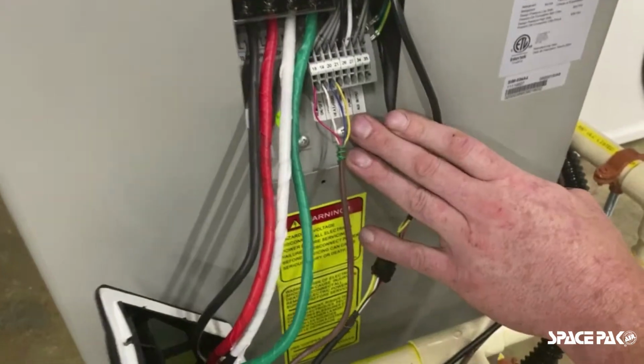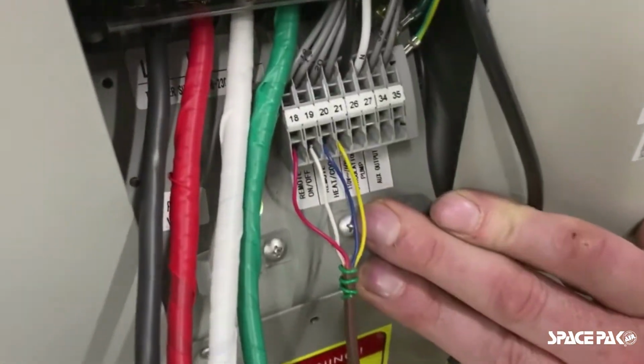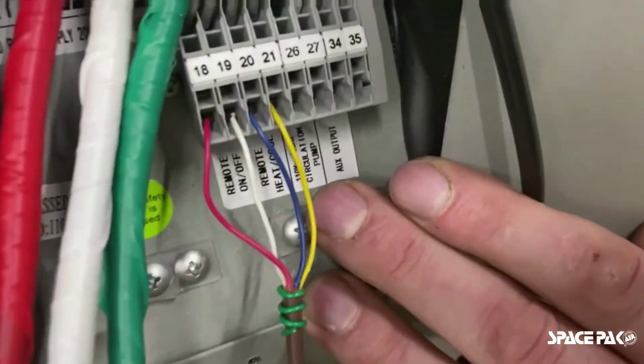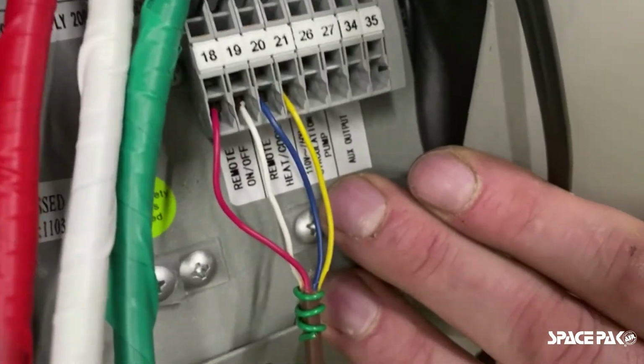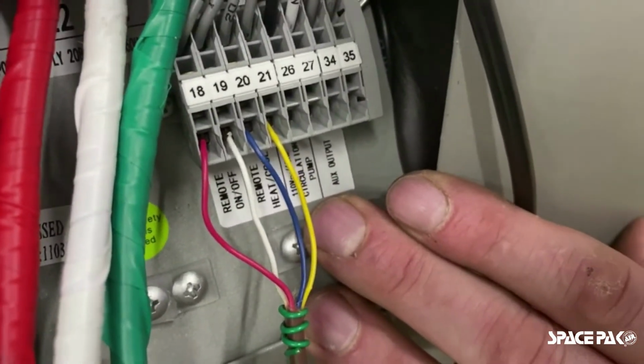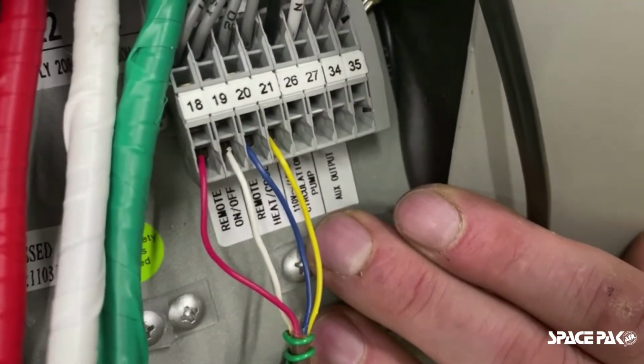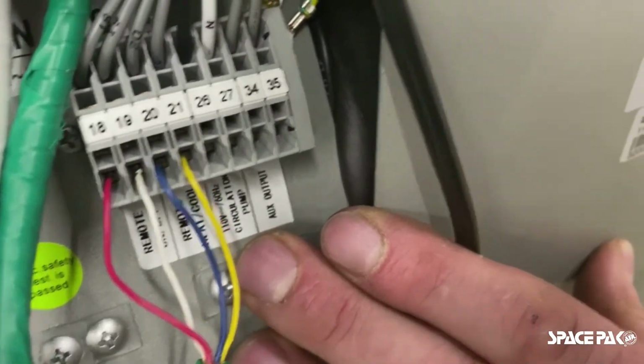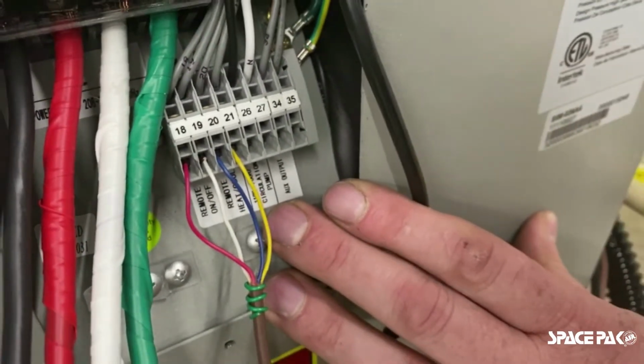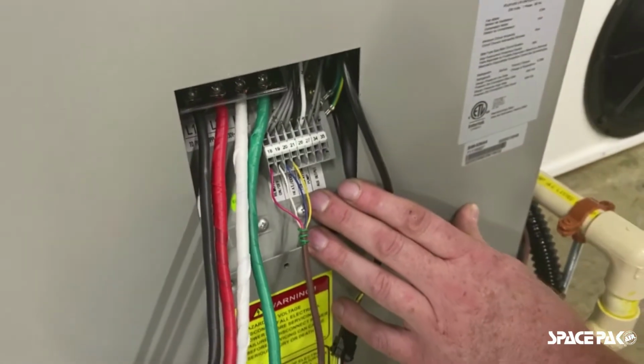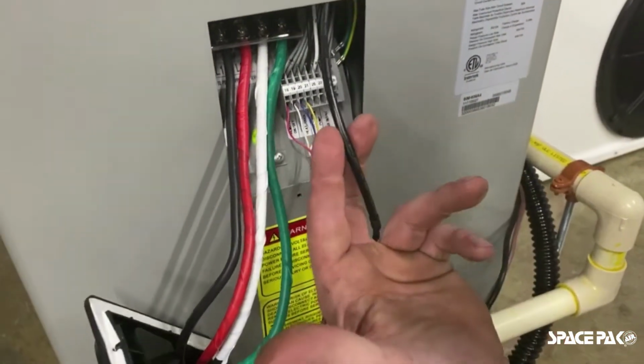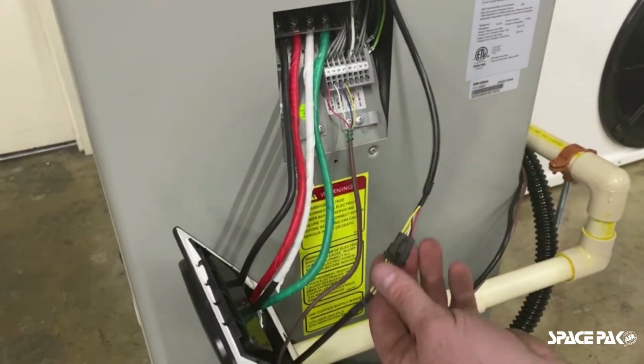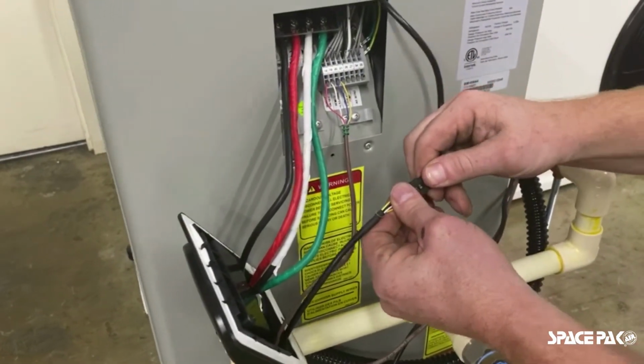Just to the right of that control, we do not have it hooked up currently, but that's where we would pick up our 110 volts required for that circulator pump. Now remember, we do need that neutral landed on the main bus bar so that we can properly operate our 110 volt system circulator. As mentioned previously, we also have our communication cable here with a connection.